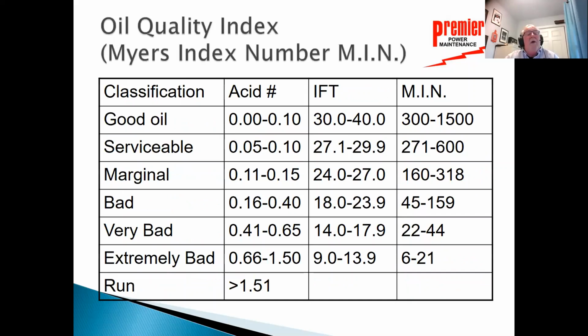There is a company called SD Myers that has done a lot of research in oil, and this is what they come up with, their Myers index number. So they look at acid and they look at interfacial tension, and basically they take the interfacial tension and divide it by the acid number and come up with a number. If that number is 300 to 1500, they say that's good oil.